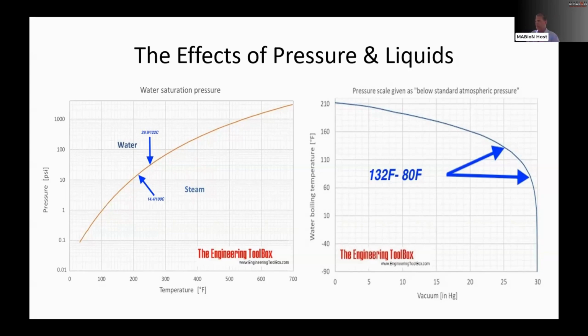So when you're sterilizing your media or your water, you can't lose it. If it boils out, it turns into just an eruption. So if you add water to the bag, is it producing steam? The answer is absolutely not. Anybody that runs liquid cycles knows the liquid will not boil. As pressure is applied, you get it up to 15 PSI or 121 Celsius, which is 250 Fahrenheit, and the pressure actually contains it to keep it from boiling.